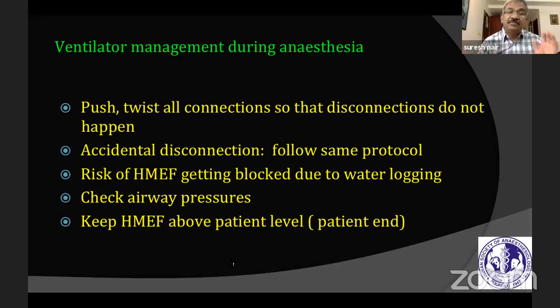When you connect, make sure you push and twist so that none of the connections become disconnected during the perioperative period. If accidental disconnection occurs, follow the same protocol: stop the ventilator, put it on standby mode, allow the patient's air to come out - though if it's disconnected, it's already come out - clamp the endotracheal tube, and then reconnect the patient.